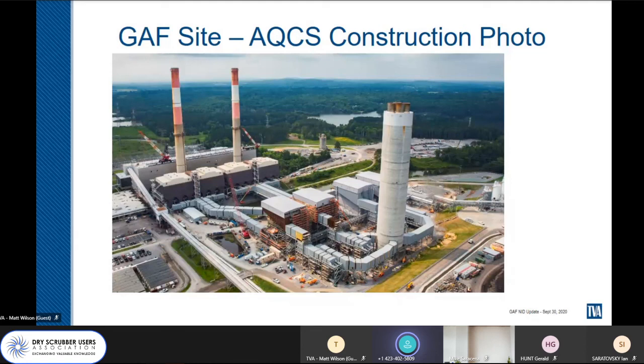The fuel utilized for the air quality control system design was a variety of fuel ranging from 100% Powder River Basin all the way up to 50% Powder River Basin, 50% Illinois Basin. That's about 0.3 to 3.1 pounds of SO2 per million BTU range out of that full spectrum of fuel. The gas flow rates coming from the powerhouse block for units 1 and 2 are approximately 1.1 million ACFM, and for 3 and 4, approximately 1.15 million ACFM. Again, 3 and 4 are a little bit larger than 1 and 2. The pulse jet fabric filter air to cloth ratios are around 3.03 for 1 and 2, and 3.29 for 3 and 4.